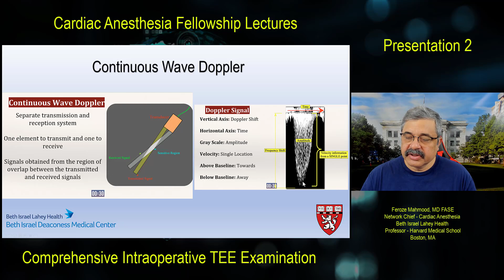So now, this is what is referred to as the demodulation of continuous wave Doppler. That is how this frequency is extracted. How do we exactly come to know what the Doppler shift is? Imagine this is the reference signal. This is the one which is being transmitted from the ultrasound transducer to assess the velocity in the line of interrogation. It is called the reference signal. Now, the detected Doppler shifted signal, which means the one that is coming back, is either of a higher frequency if the target is moving towards, or a lower frequency if it is moving away. Now, both these signals are multiplied. This is called signal multiplication or mixing, to understand how much they are out of sync with each other, and that determines the Doppler shift.